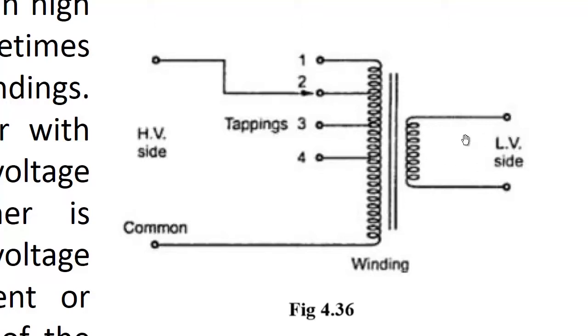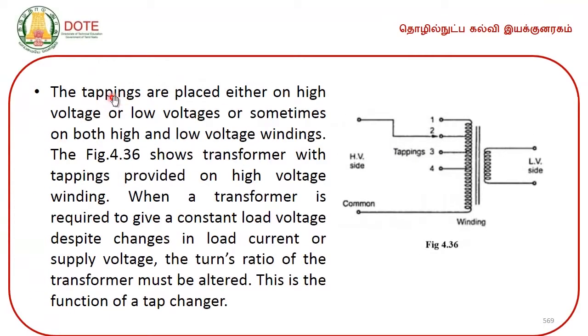So, this is the LV side, which has no tapping in this configuration. The tappings are placed either on the high voltage or low voltage side, or sometimes on both high and low voltage windings. Figure 4.36 shows the transformer with the tappings provided on the high voltage winding.